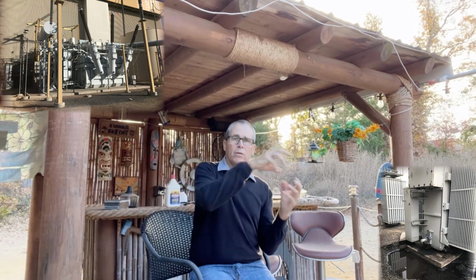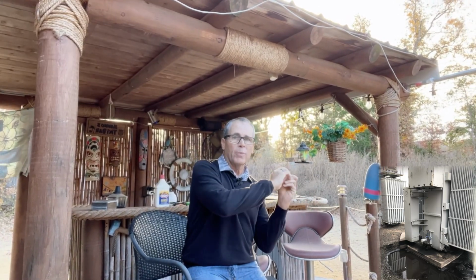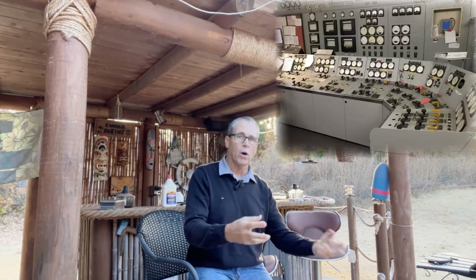From a risk standpoint, we looked at it: if the small transformer catches fire—this was an auxiliary transformer for the site, much smaller than the generator step-up transformer. The generator step-up transformer provides the power leaving the plant, while the auxiliary transformer provides the power that goes back into the plant for the lights, controls, pumps for the water, and other in-house loads.